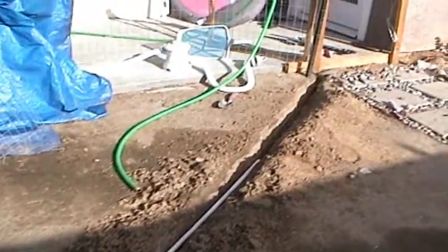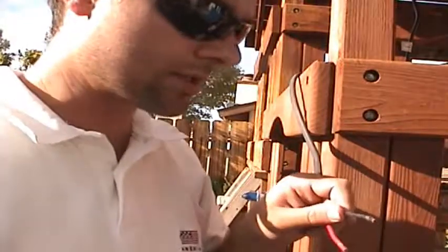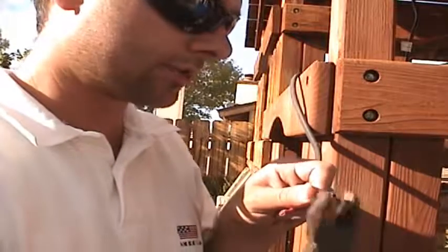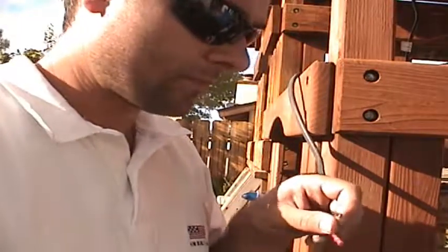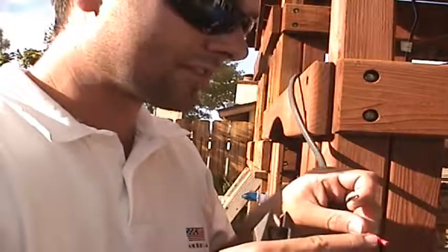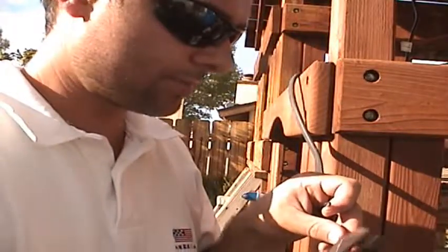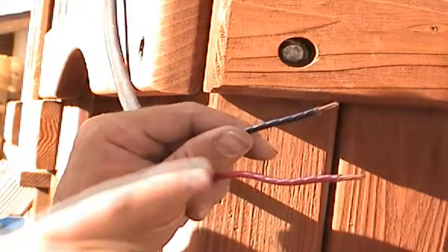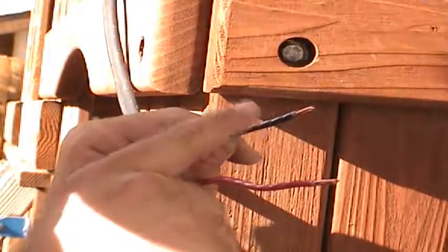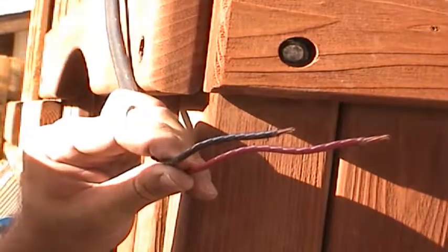Now that I've finished running my outdoor cable through the PVC pipe, I'm going to go ahead and connect this end to our solar panel combiner box. Before we install the outdoor cable into the combiner box, let's do two things. First, let's cut an inch off of the black conductor. And then let's remove about a ½ inch of skin from both the red and black conductors. We can use our wire cutters to do this as usual. Now that we've removed a ½ inch of skin from both the red and black conductors in the outdoor cable, let's go ahead and install these cables into the combiner box.